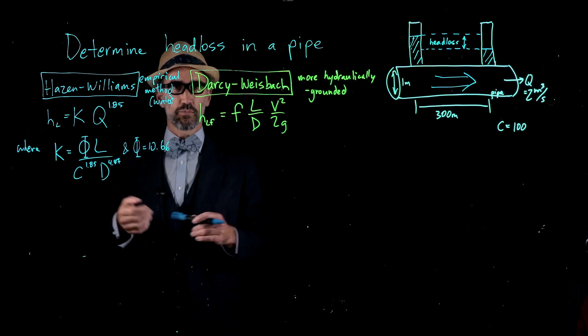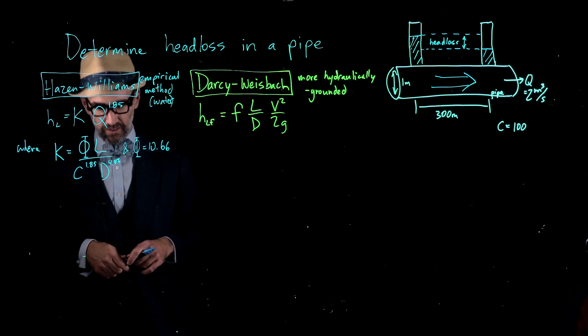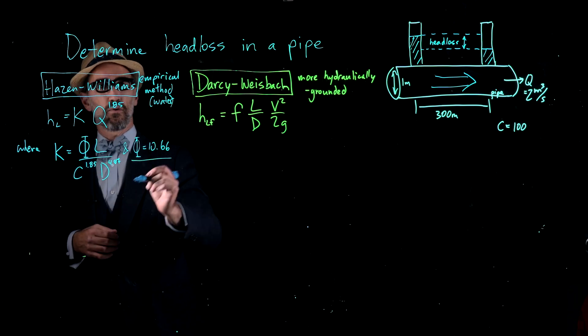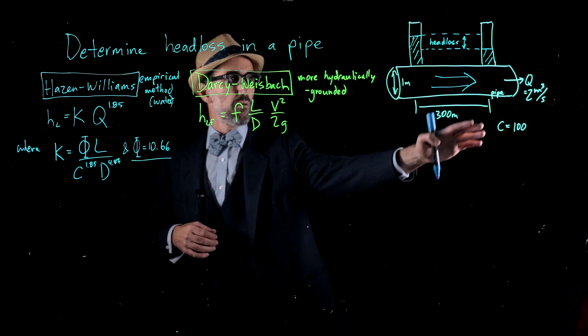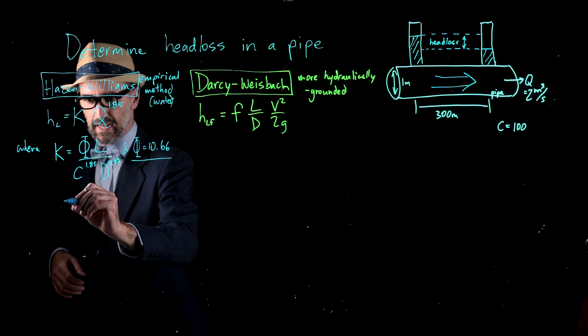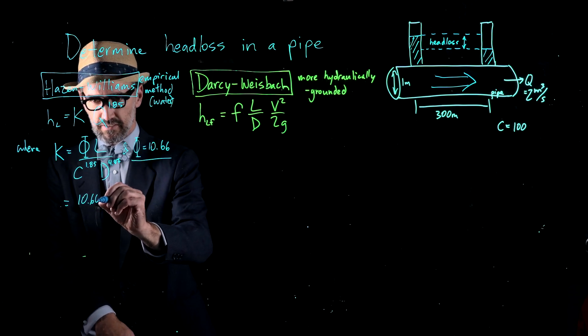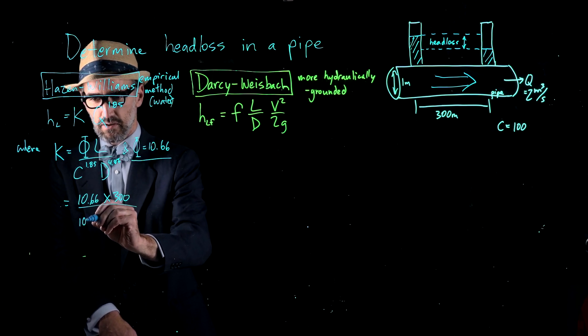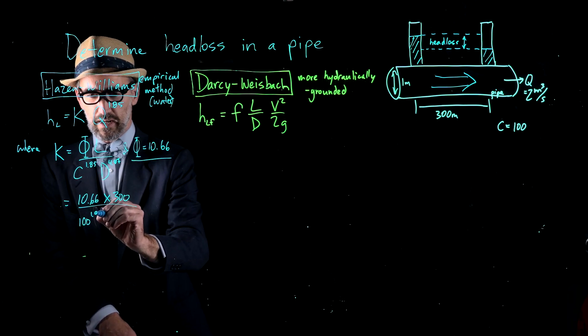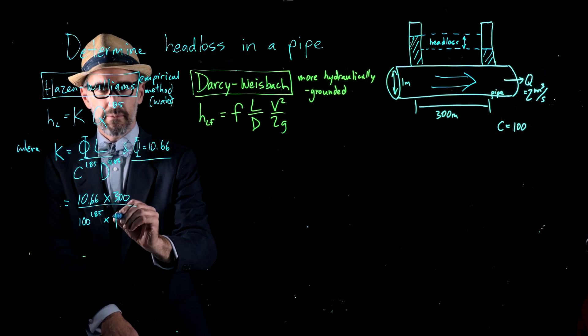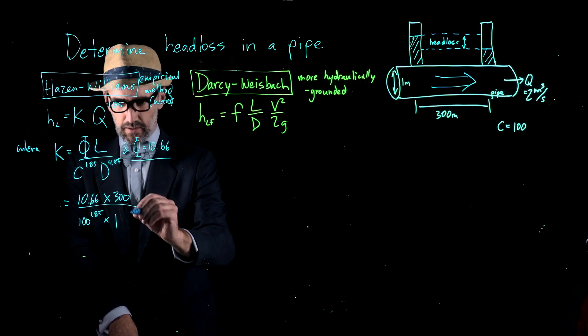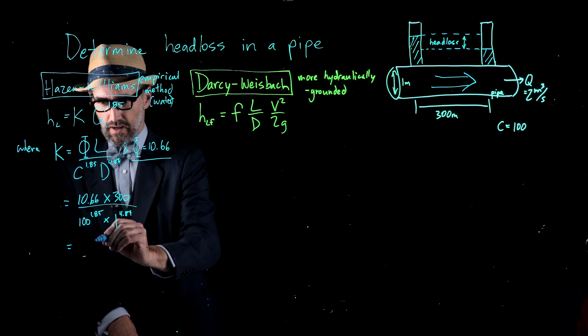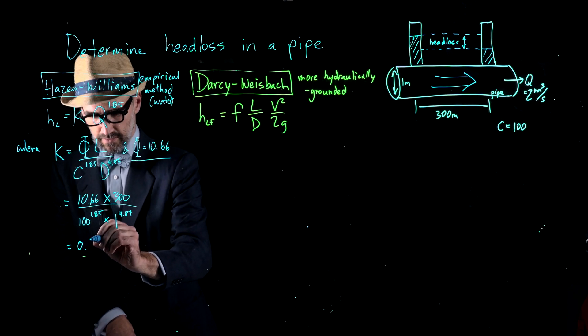These are unusual exponents because this is an entirely empirical equation, again only for water. This Phi is the coefficient for metric units, which is what we have here in meters. To solve for K: K equals 10.66 multiplied by the length of 300, divided by C — which is 100 — to the exponent 1.85, multiplied by D — the diameter of 1 meter — to the exponent 4.87. This results in a K value of 0.638.